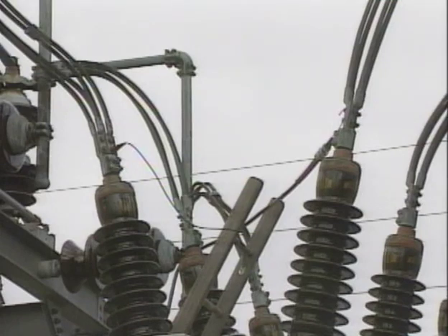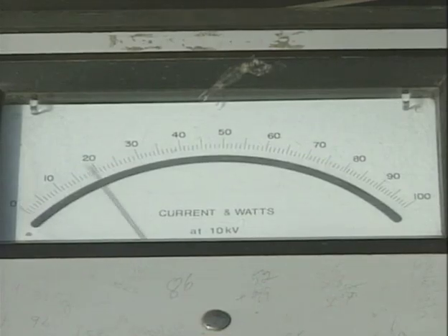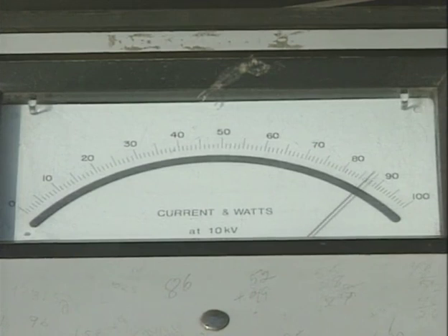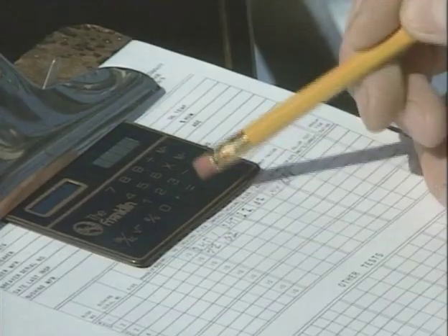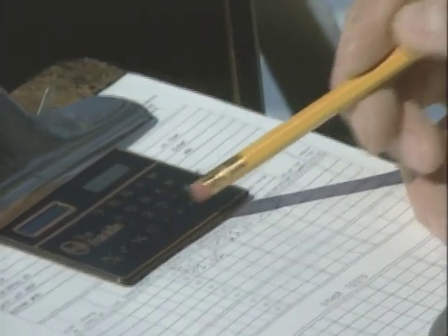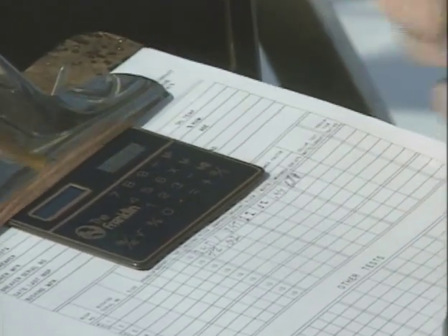The purpose of a power factor test is to determine the condition of the electrical insulation of the circuit breaker. In principle, the test is performed by applying a high AC voltage across the breaker bushing terminals. With the breaker contacts open, leakage current is measured across the open contacts in both directions. With the contacts closed, leakage current is measured across the closed circuit to ground. The test instrument measures milliamps and watts. These values are documented. They're also used to perform calculations to determine the power factor of the breaker insulation.